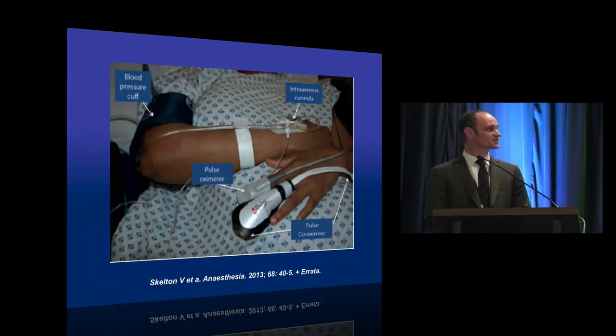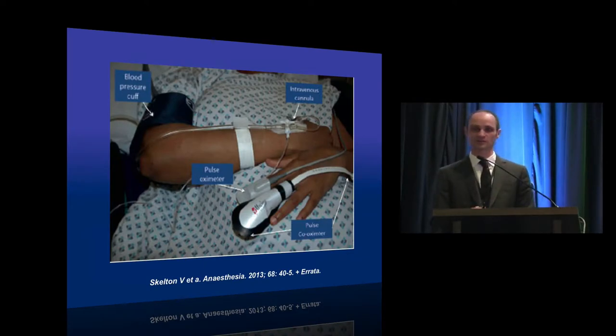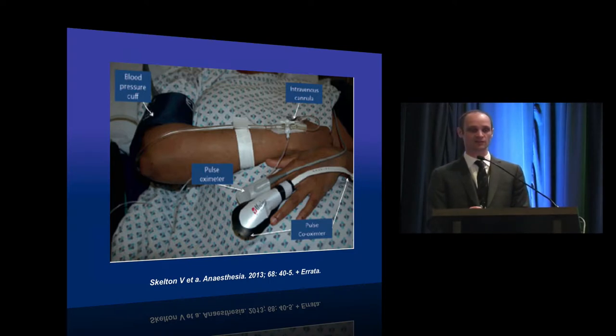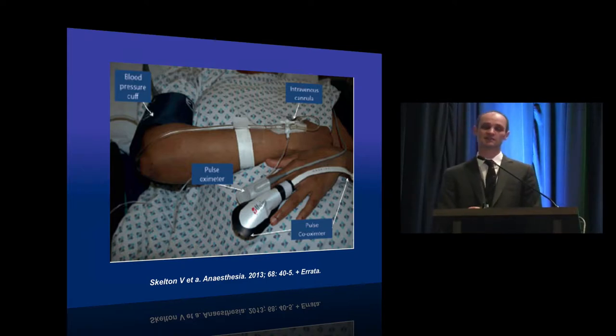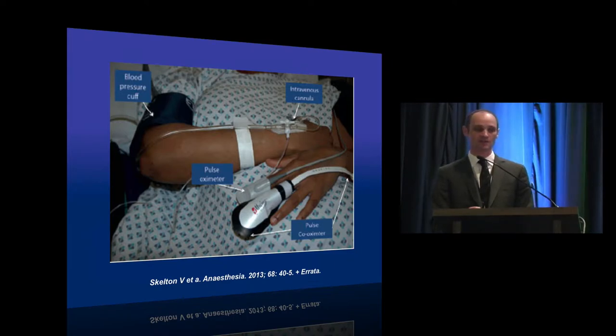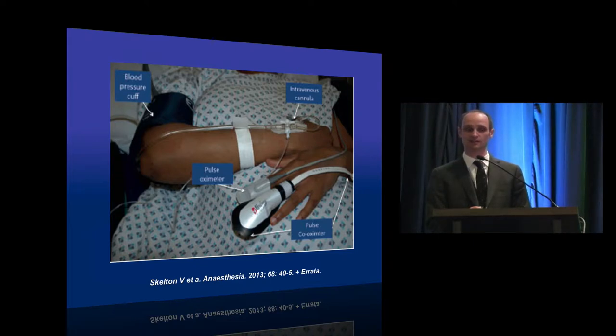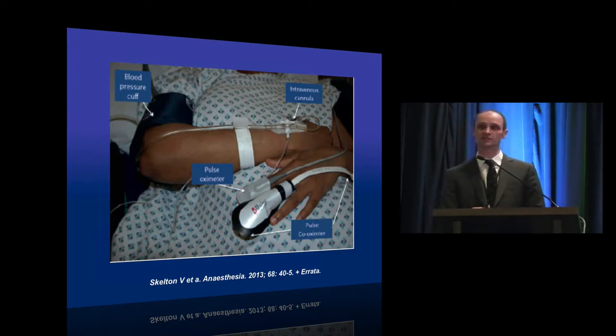On this slide, we can see a typical setup when using this device from a clinical or research standpoint. You can see the device on the middle finger of the patient's left hand. A black sheath or hood is mounted on top of the probe to avoid interference with ambient light, and the white interconnect comes out from underneath. Note that the device is on the hand that doesn't have the IV or blood pressure cuff, to avoid interference.